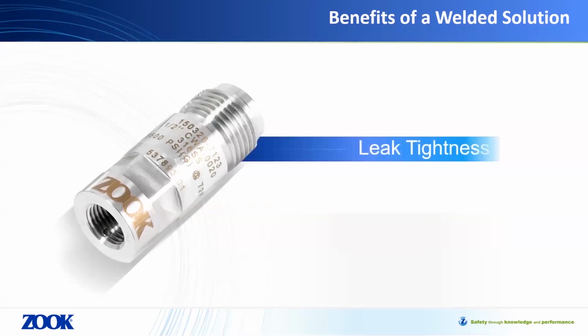The first benefit is leak tightness. I know that I had already mentioned leak tightness as one of the values of using a rupture disc, but the welded products team really takes this to the next level. Traditionally, when we talk about leak tightness, we think about a bubble leak. Welded products go far beyond this bubble leak tightness, as the welding process has the ability to melt both the rupture disc and the housing components together to provide the most robust hermetic seal available.